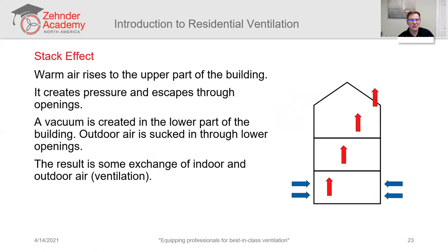So the warm air rises to the upper part of the building. As it does, it creates pressure in the upper part of the building and it escapes through the openings in the upper part of the building. And as that happens, a vacuum is being created in the lower part of the building. And so the outdoor air is being pulled in. Now this isn't necessarily due to wind, although wind could be in combination with this, but just through this natural stack effect, you're pulling outdoor air into the building.